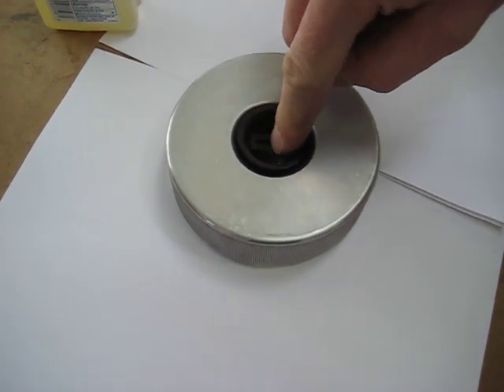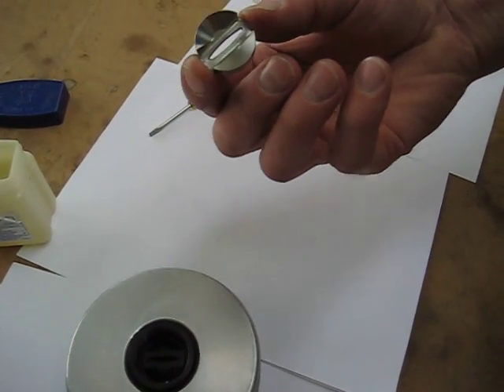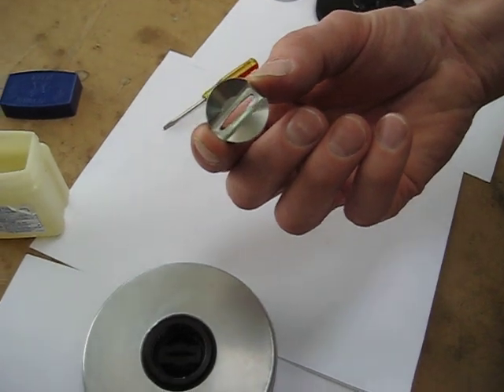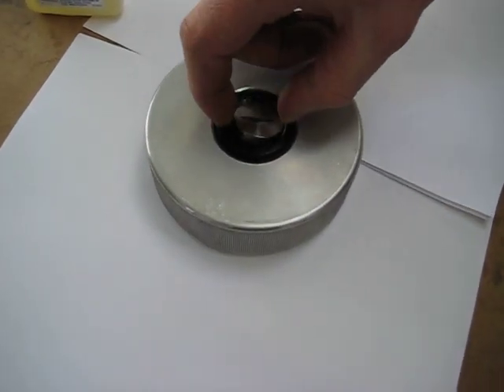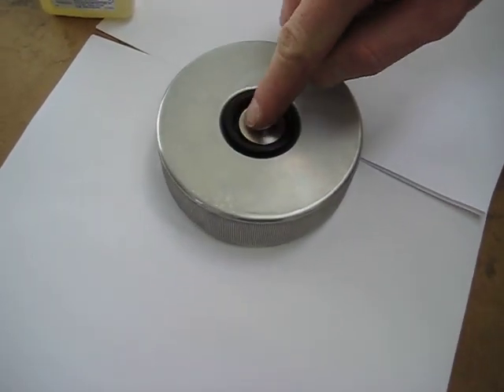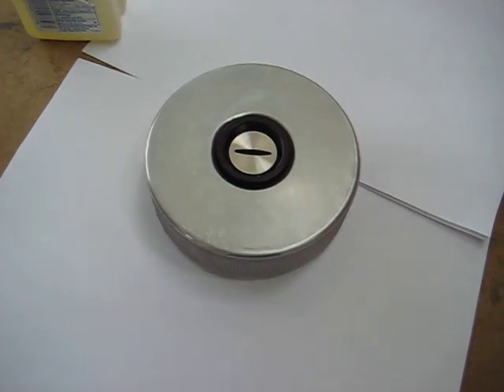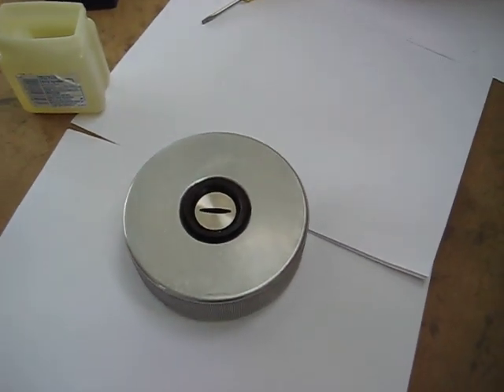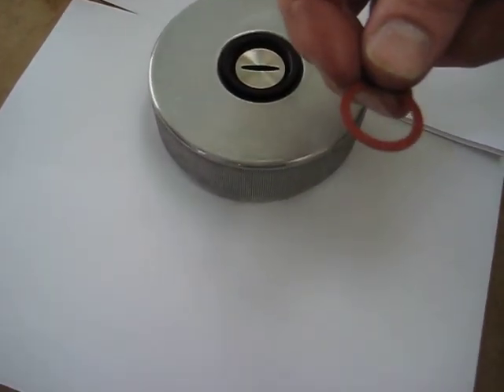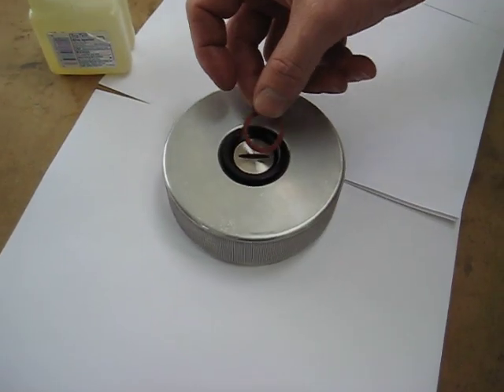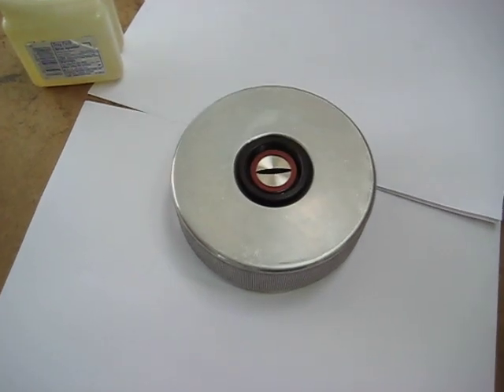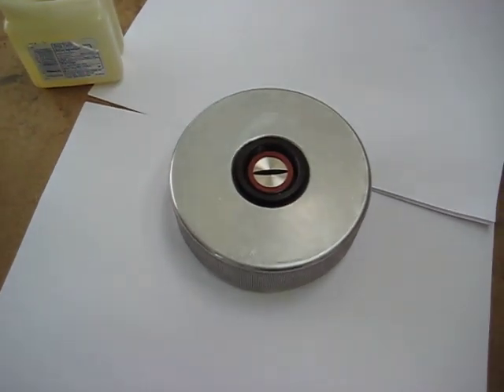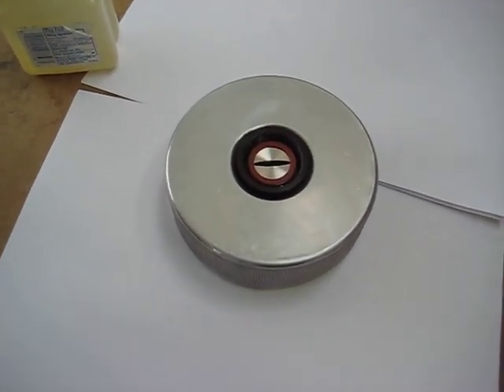We're just going to line that up. The insert is going to go concave side down, flat side up to match the gasket. Then we're going to put in a friction washer on top of that. The friction washer simply keeps the two parts, the screw and the insert, from galling each other.